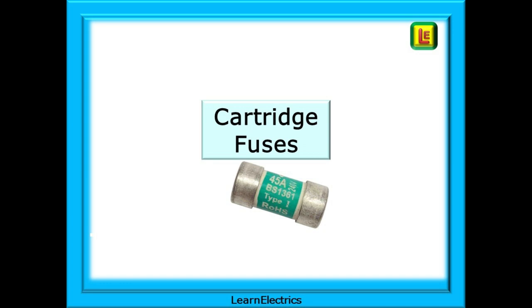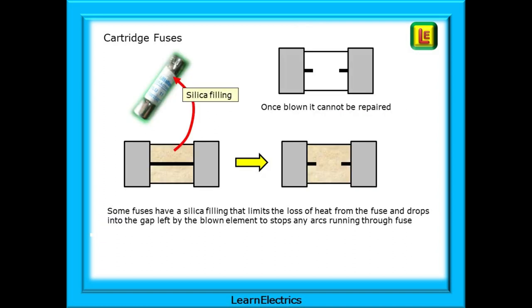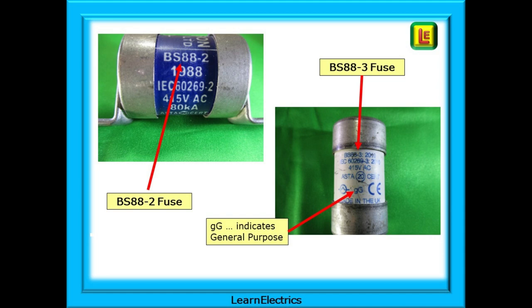Cartridge fuses are very popular and we should look at these next. The fuse element in a cartridge fuse is an accurately blended alloy of different metals and elements, very accurately sized so that the required accuracy and repeatability can be achieved. Each size and type of fuse will have its own unique response to currents that flow through it — such as how quickly it will melt, and whether it will react to motor start-up surges. It's easy to choose the correct size fuse, easy to change, and they have much more accurate fusing. Once blown, a cartridge fuse cannot be repaired — there will be a significant gap between the two end caps and current will not flow. Some fuses have a silica filling that limits the loss of heat from the fuse and drops into the gap left by the blown element to stop any arcs running through the fuse — arc quenching.